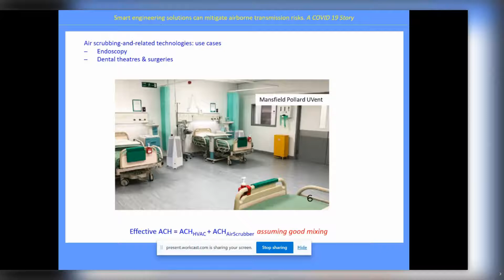Another device, there's one of these on the wall of One Birdcage Walk. You can look at it next time you're visiting the institution. It's a different orientation, but it's a pushing fan which takes air from the bottom, drives it through a chamber. The chamber is lined with aluminium, which is highly reflective to ultraviolet light in the wavelengths of our interest, about 254 or so, and expels it from the top.